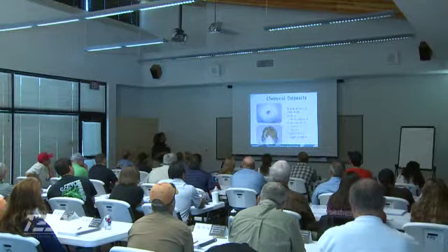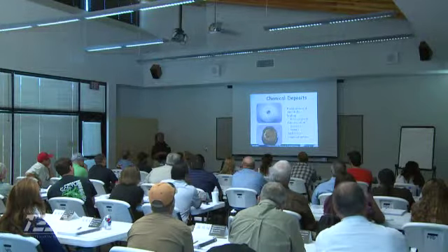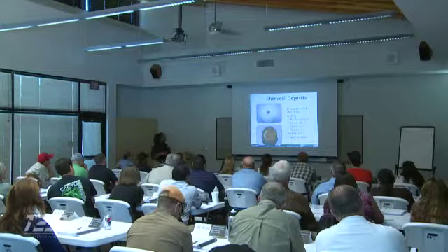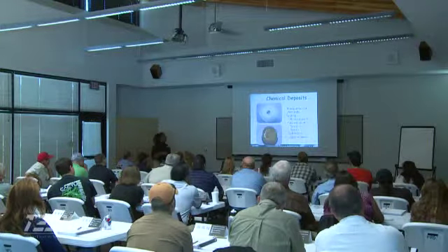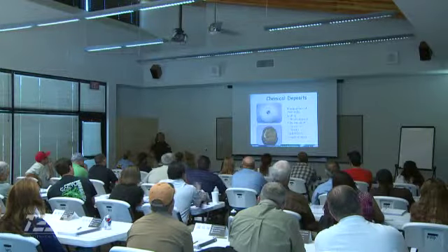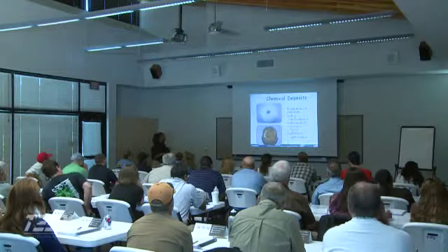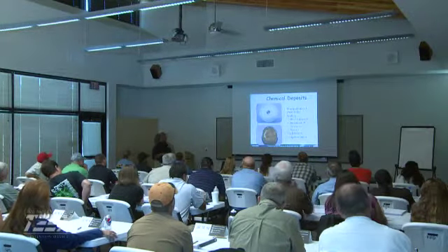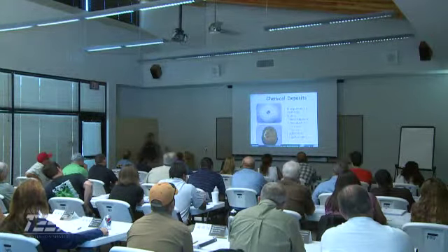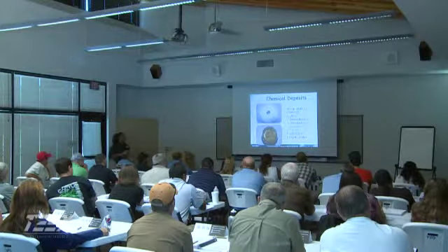Tuberculation is where we have nodules built up, and this one here is really bad. Usually you can see through it. But you have the barnacles and nodules. Again, one of the ways that we're going to use as an operator process tool is to utilize the Baylis curve or the Langelier index to determine whether or not we have corrosive or scale forming water.